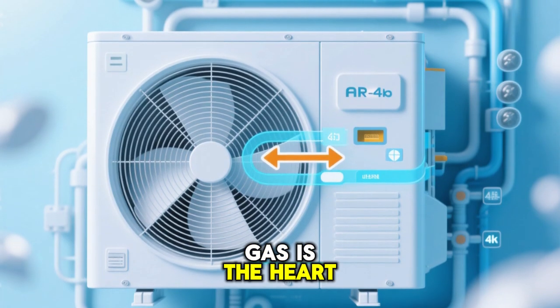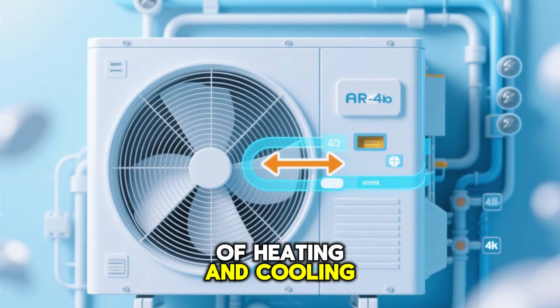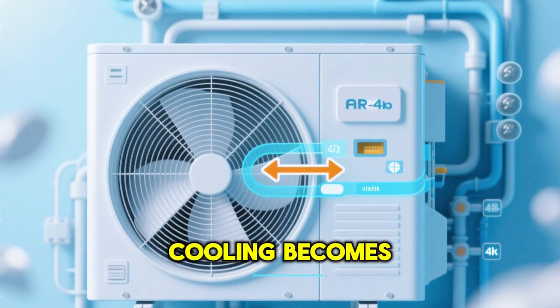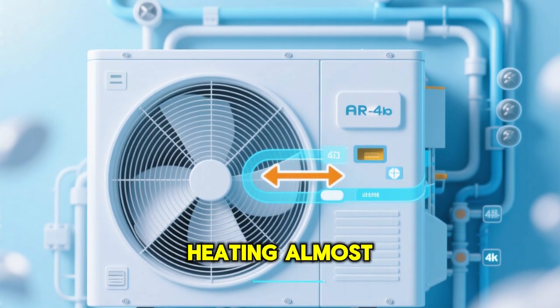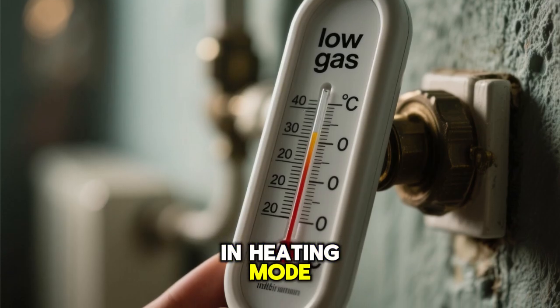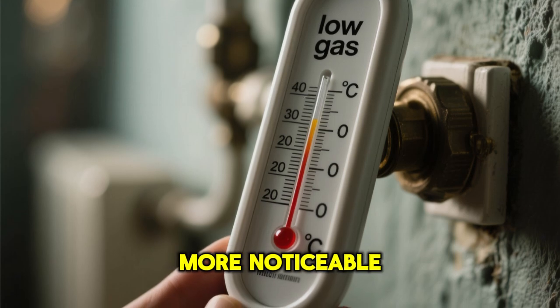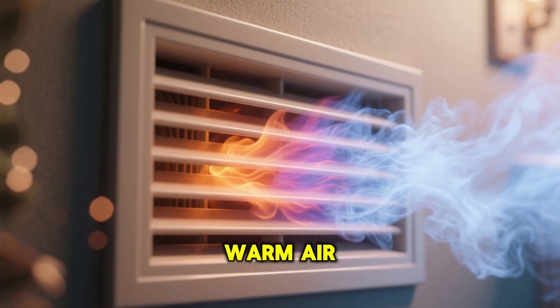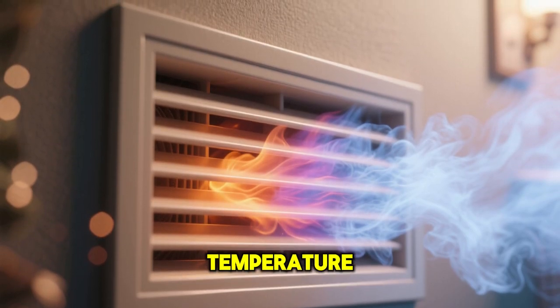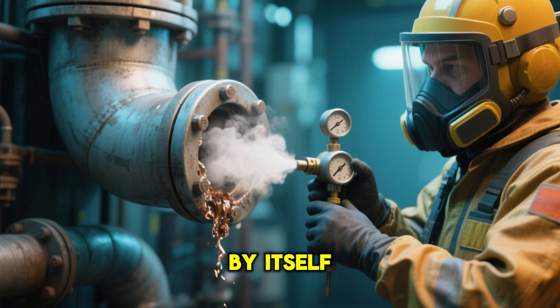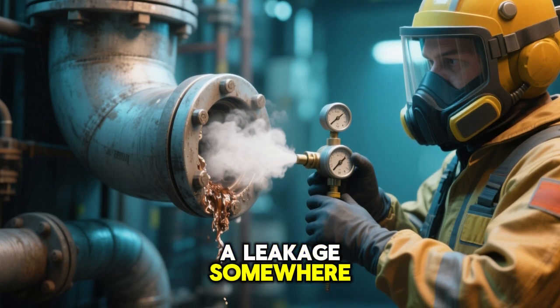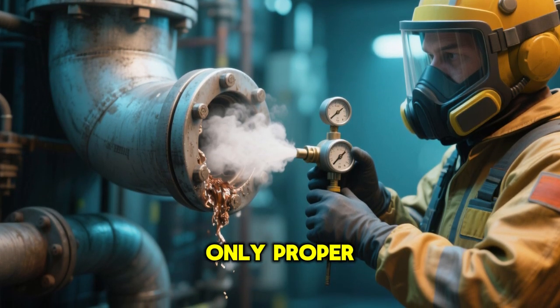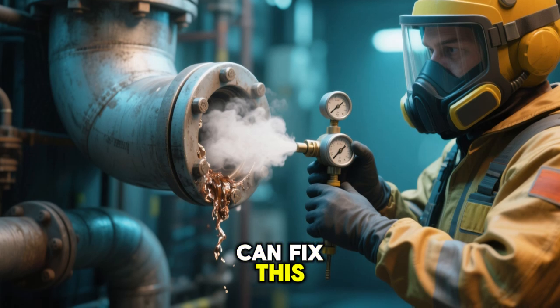Refrigerant gas is the heart of heating and cooling. When gas level becomes low, cooling becomes weak, heating almost disappears. In the heating mode, low gas problem becomes more noticeable. You may feel slightly warm air at start, then it becomes normal temperature. Gas does not disappear by itself. It means there is a leakage somewhere. Only proper pressure testing and vacuuming can fix this.